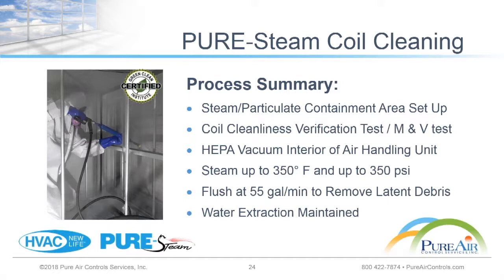So it's a very professional process. Our guys are trained in unique techniques about what angles to hit the coil at, hitting the coil from both sides. We actually have a training facility here with an air handler and duct system developed specifically for training our technicians in steam cleaning coils and cleaning ductwork.